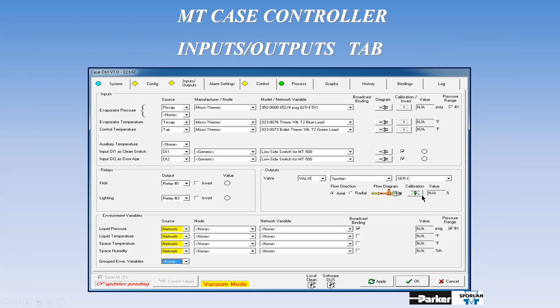I've chosen that as an SERC, and I've chosen that the flow is axial, meaning that if you looked at this as a gyroscope or a spinning top, it's coming in on the axis. If it was coming in on the side, it would be coming in on the radius. That's why we call it radial. But guess what? It makes a slight difference on the capacity of that valve depending upon how it's piped. And we can make a correction. We can also do a calibration correction. All right. Any questions on this at all?